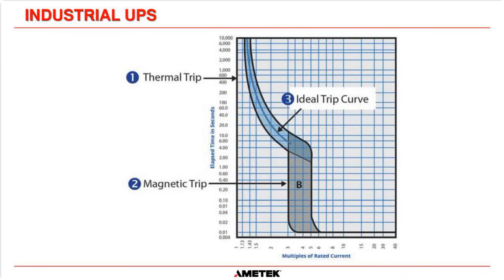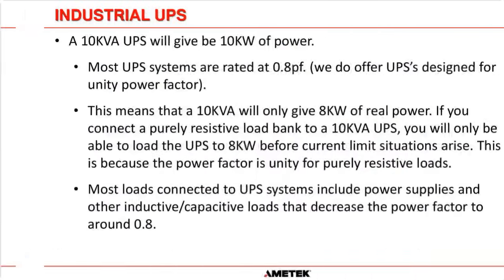In most scenarios that I have found, every time we replace a UPS with a 208 UPS, it's because the original UPS was a 208 volt UPS, and there's a 208 volt distribution panel on the wall, and you don't want to go through the process of changing that panel to a 120 volt single phase panel. And I understand it, but I just wanted to make it clear why a single phase UPS is usually always better than a 3-phase UPS.